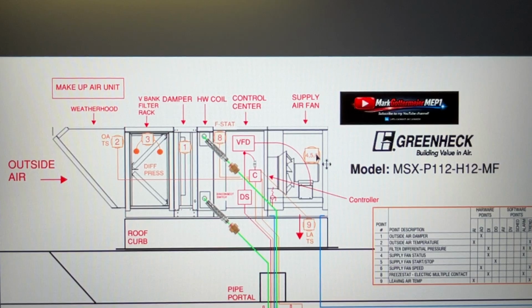And then 4, 5, and 6 are all fan related, so those are all right here at the fan. Our freeze stat, like I said, is on the discharge side of this coil. And then our leaving air temperature sensor will be a probe down here where the treated air is pushed down to the space.